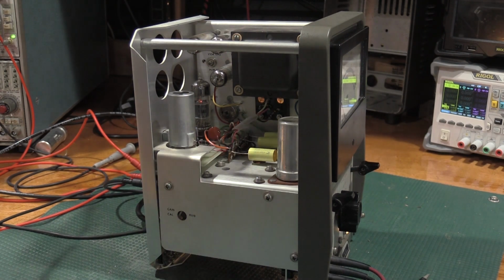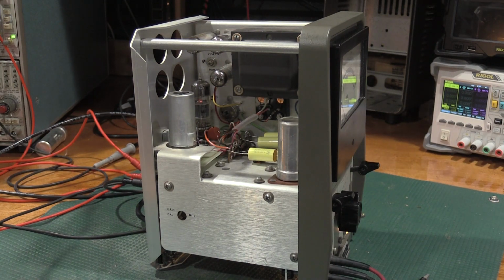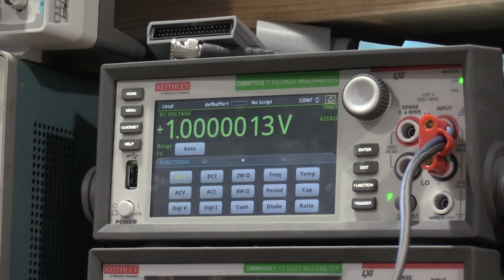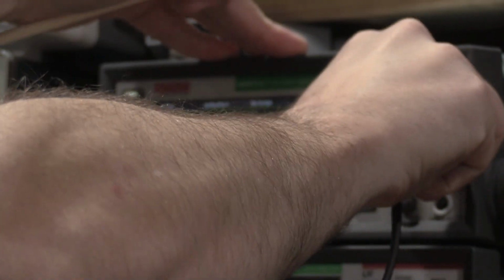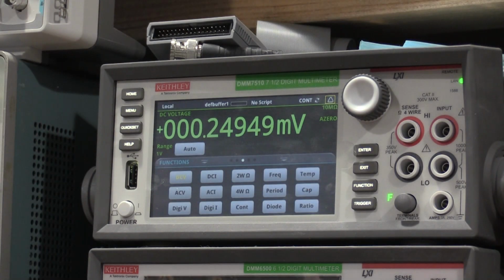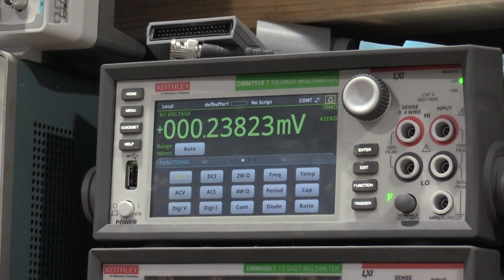Okay, it does not tell you to 0 the meter at the beginning of this process, but you do need to do that. We have a very good 1 volt coming out of the voltage calibrator, as checked on the 7510. So what I need to do now is unhook this, because this is only a volt, so we can touch this without worrying about it too much. And then we need to hook up the DC amplifier.